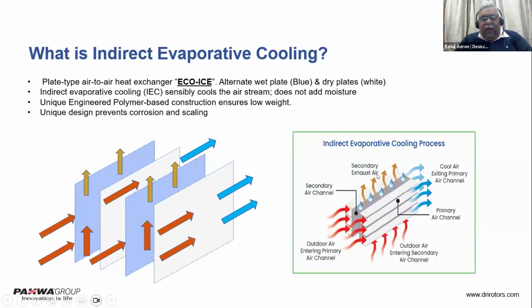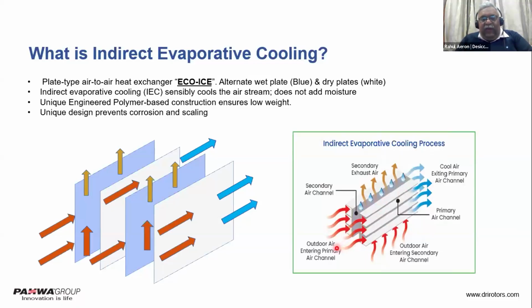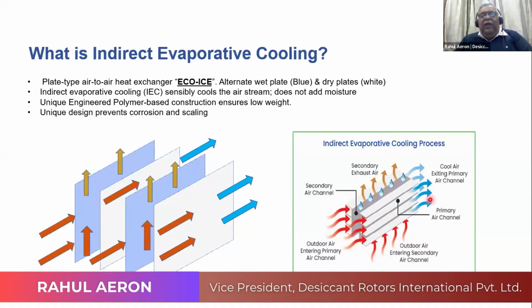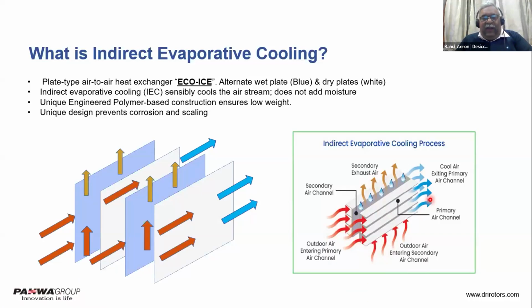So if you see on this right side, we have this heat exchanger here. It has two air streams. This is what we call the primary airstream, and then there is the secondary airstream. So typically, let's say I want 100 units of air here. I would design this fan for 135 units, and the 35 units of air is used as the secondary air. Now, this secondary air is coming in contact with water, and it is evaporatively cooled. So only the secondary air, only the 35% of the total air quantity, is evaporatively cooled, and the majority of the air which is going from left to right is cooled only sensibly. Sensibly means only the temperature is going down. There is no moisture being added. So this is what we call an indirect evaporative cooling system, wherein only the temperature is reduced and no moisture is added. So that's where you can address that problem of humidity control in the conditioned space by using an indirect evaporative cooling system.